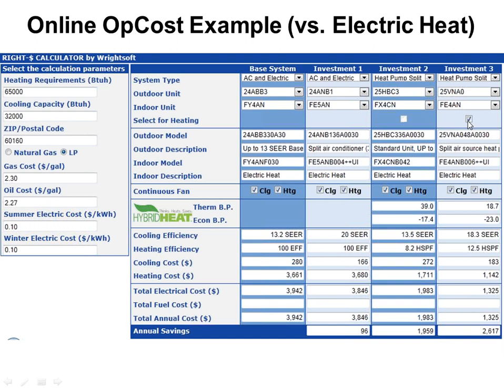On the variable speed heat pump, I can check it because in the summertime he can ramp down, in the wintertime he can ramp up. And what that does is try to upsize my heat pump closer to my heating load. So instead of a 32,000 BTU cooling load, which would have given me a 3-ton or 2.5-ton heat pump, this guy put in a 4-ton heat pump, 25VNA048. So that's why he's able to get down to those lower outdoor air temperatures. So hopefully that answered the question. If not, Jim, I think you asked the question, just contact me afterwards and I'll clarify it even further if we need to.